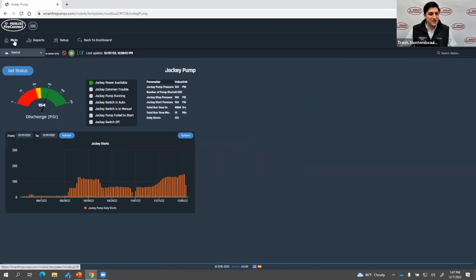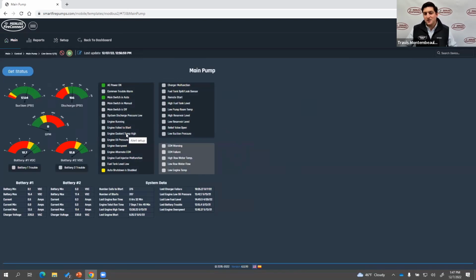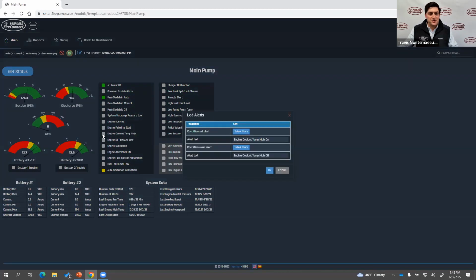So as part of the demo, let me go back to the main pump for a second here. We talk about this Modbus enabled controller versus a non-Modbus enabled controller, and you pick up all these additional data points here. And these are all alertable. So if I want to get a text message if my engine coolant temp is high, I click where the LED is here, set a condition based on that LED turning on, and say, send me a text message. And if I'm out on vacation, I can say, if I don't answer this text in 30 minutes, send it to this next person.